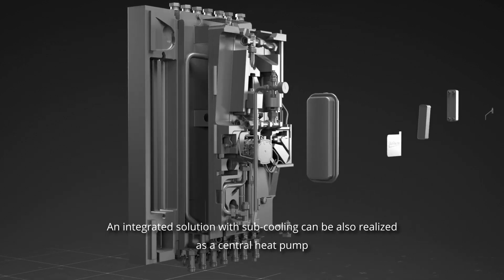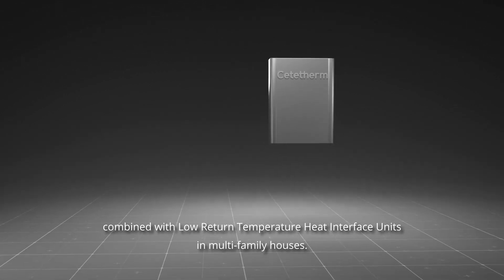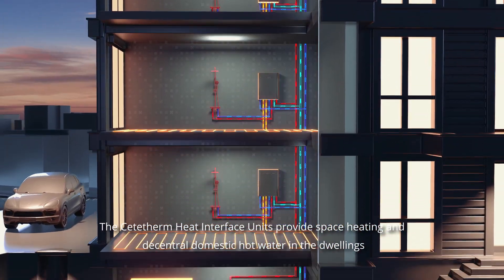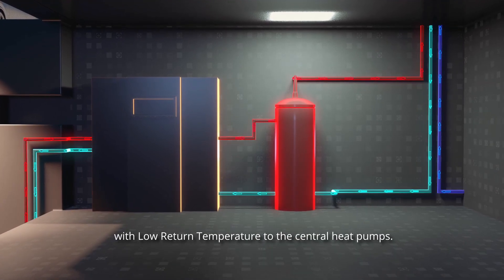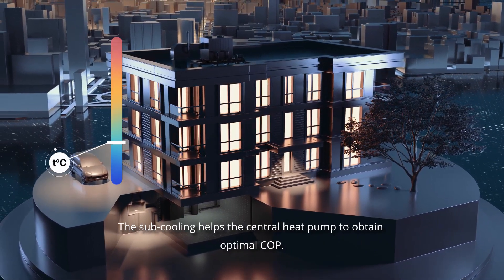The sub cooling is reached thanks to Cetetherm Aqua Efficiency supplying continuously low return temperature to the heat pump. An integrated solution with sub cooling can also be realized as a central heat pump combined with low return temperature heat interface units in multifamily houses. The Cetetherm heat interface units provide space heating and decentral domestic hot water in dwellings with low return temperature to the central heat pump, helping it obtain optimal COP.